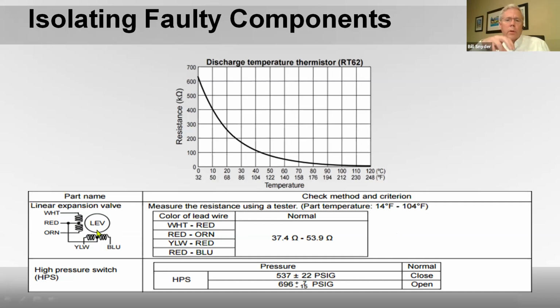I've seen where that's actually popped off in shipping and we're getting some weird issues, it's not cooling or heating properly. You go in there and you find that it's popped off of its port. It just literally has a little clip that pushes it down into place. Now they've been taking a wire tie to it and tightening it down so it really can't pop off, but that's just something to check if you're getting some erratic readings.